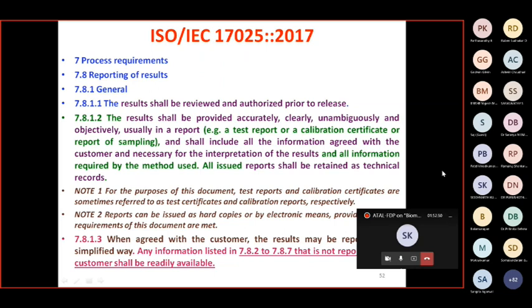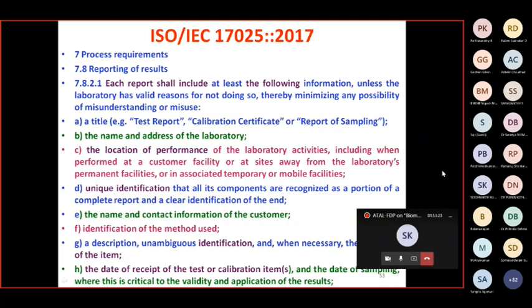So initially we would have agreed with the customer on the components of a test report, and we ensure all those points are mentioned. Sometimes the customer will say, don't give a 2-page report, it takes a lot of time for me to read. Give me a 2-line report, whether it meets the requirement or not. Details, if required, I will ask you. You can agree upon that and give a simplified report to the customer. However, you will retain all the data for a reasonable time, which is agreed between you and the customer. In case he wants it for any investigation or future reference, you may have to supply the data.